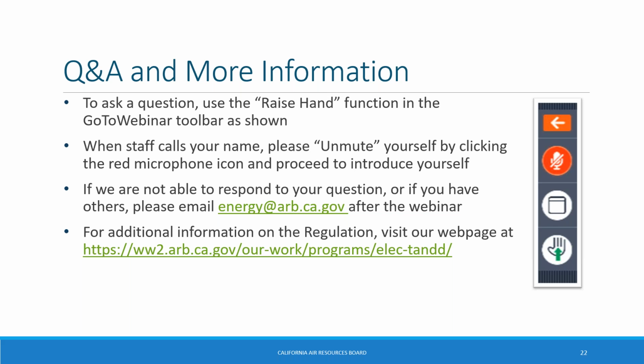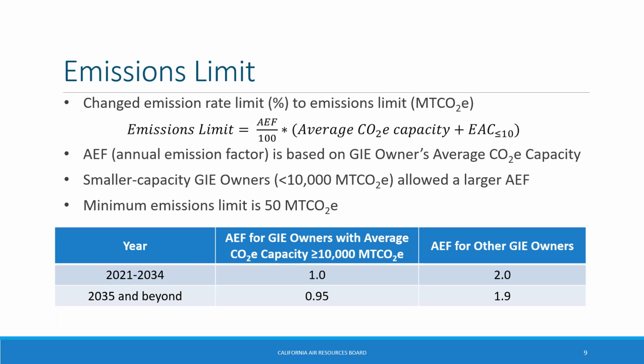Hi Raul. Yeah, so the new emissions limit under the amended regulation is a little different than the old emission rate limit we had under the original regulation. Under the new regulation, every GIE owner's emission limit will essentially be 1% of their system capacity if their system capacity is greater than or equal to 10,000 metric tons of carbon dioxide equivalent. For those GIE owners, and we have the equation up here on the slide, the new emissions limit should be about the same as the old emission rate limit in terms of how much SF6 can be emitted. This new equation also integrates the early action credit.